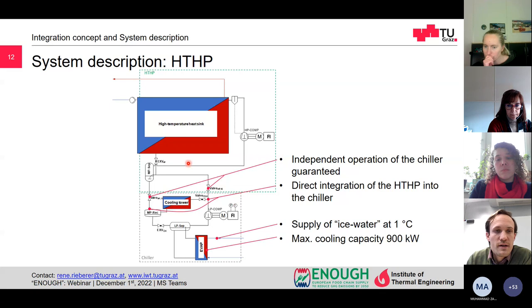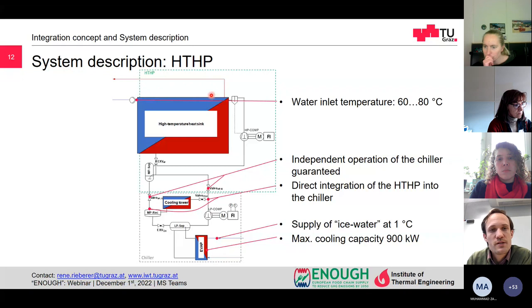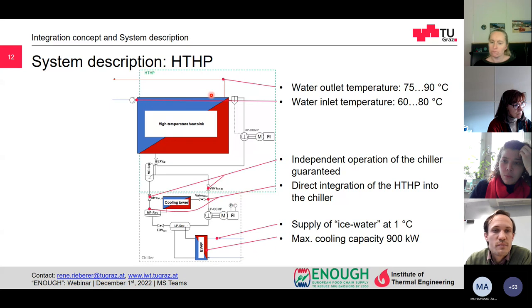And the heat of the high temperature heat pump is rejected to the high temperature heat sink, which is used here for the cleaning in place system. The water inlet temperature, the design temperature, is around 60 to 80 degrees Celsius, and the outlet temperature of the hot water is approximately 75 to 90 degrees Celsius.